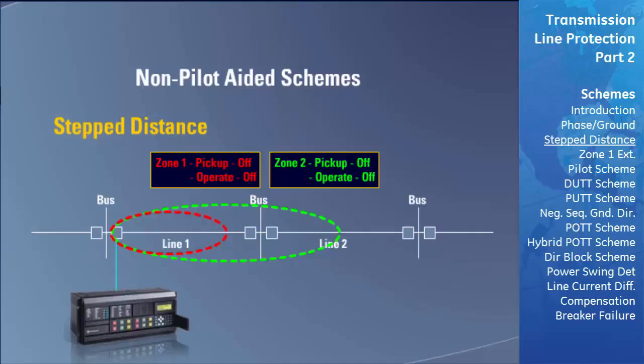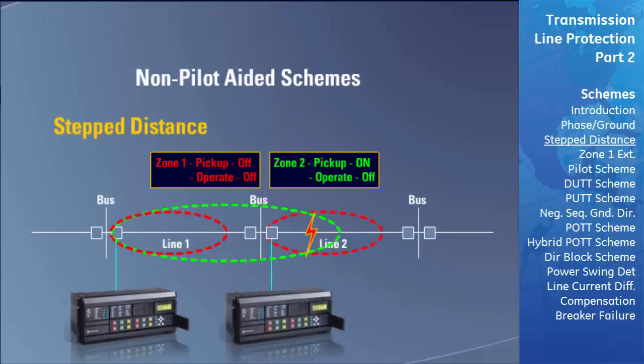You may wonder what happens if a fault occurs on the adjacent transmission line but still within the zone 2 area of protection. Normally, after the zone 2 time delay expired, the relay would trip the unfaulted transmission line. However, every adjacent transmission line is protected by its own distance relay. This fault would fall into the second relay's zone 1 of protection, and the fault would be cleared before the timer of zone 2 in the first relay expired.